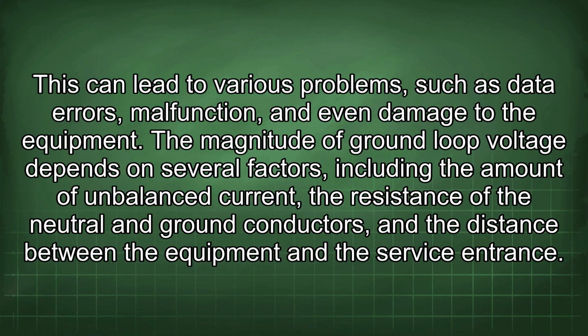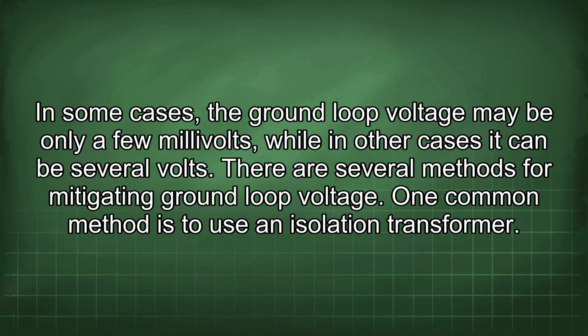The magnitude of ground loop voltage depends on several factors, including the amount of unbalanced current, the resistance of the neutral and ground conductors, and the distance between the equipment and the service entrance. In some cases, the ground loop voltage may be only a few millivolts, while in other cases it can be several volts. There are several methods for mitigating ground loop voltage. One common method is to use an isolation transformer.